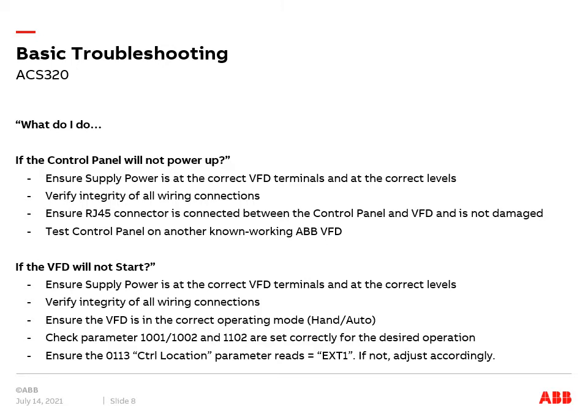What if my VFD is powered up but the VFD will not start? Similarly, you want to ensure the supply power is at the correct VFD terminals and at the correct levels, and verify the integrity of all your wiring connections.